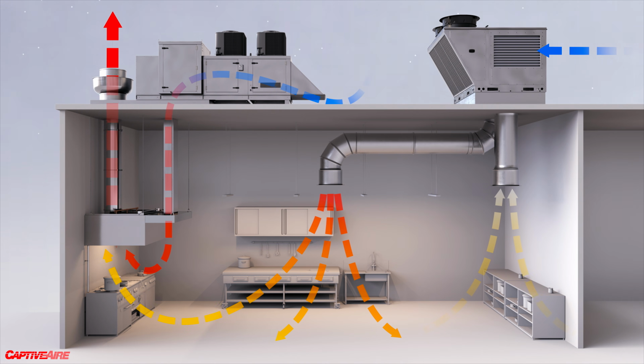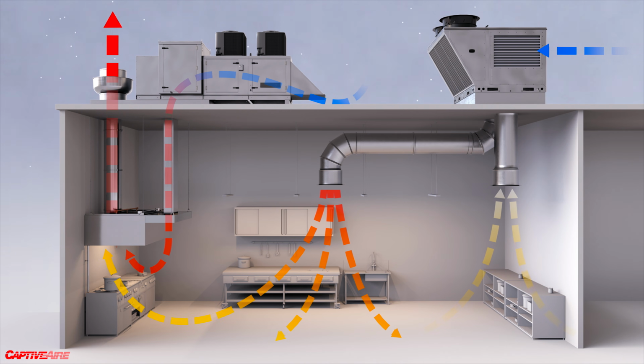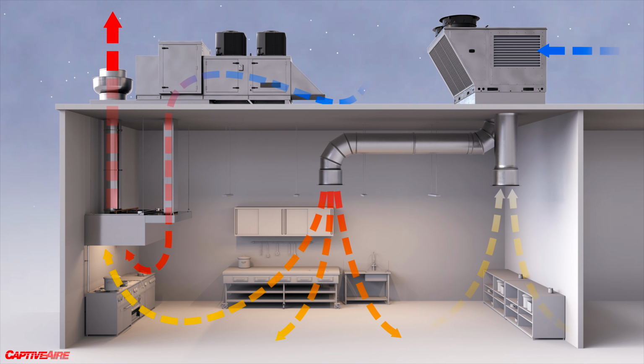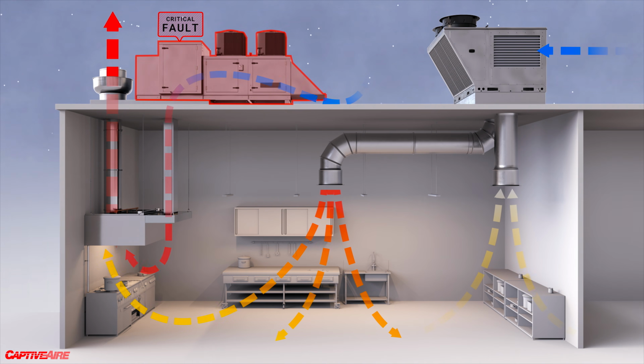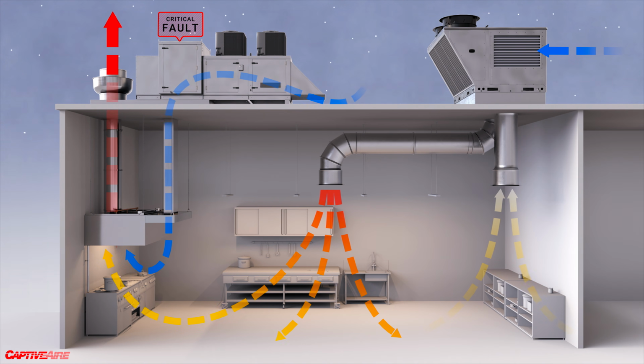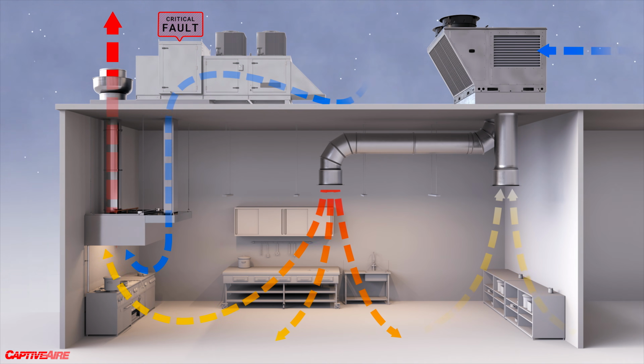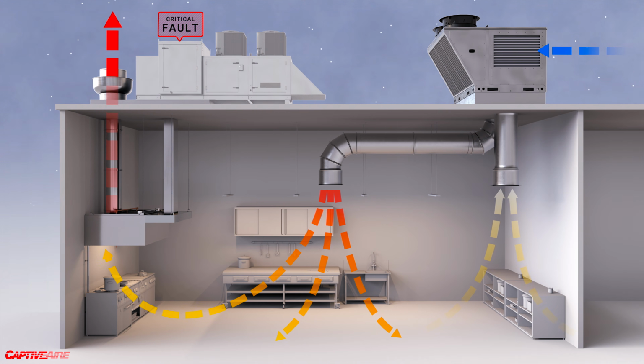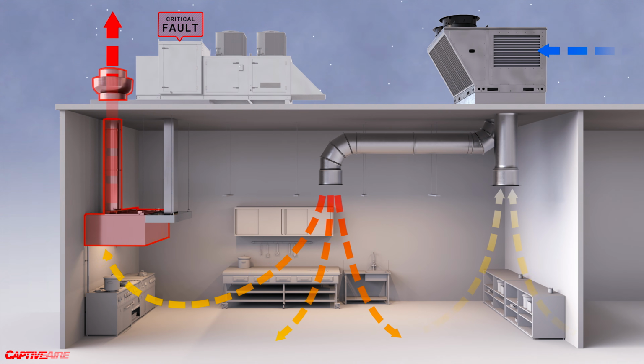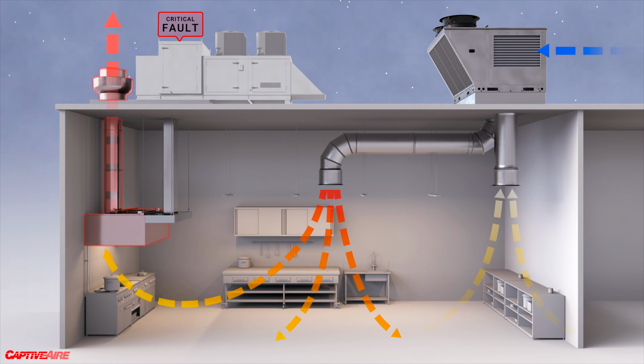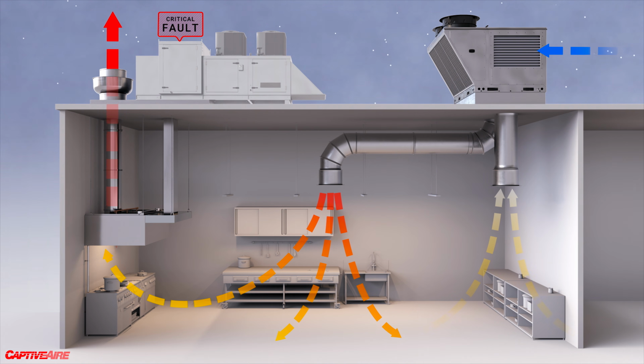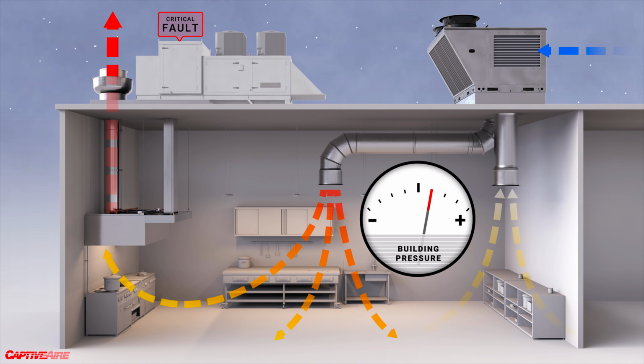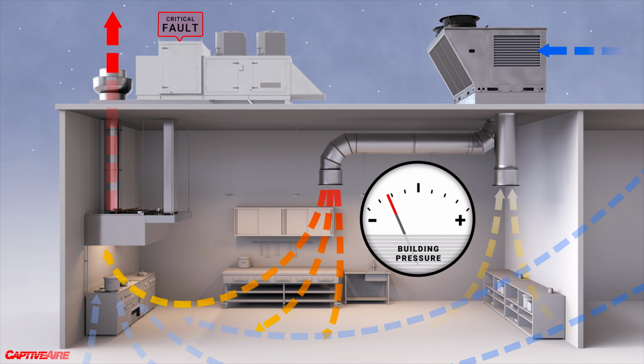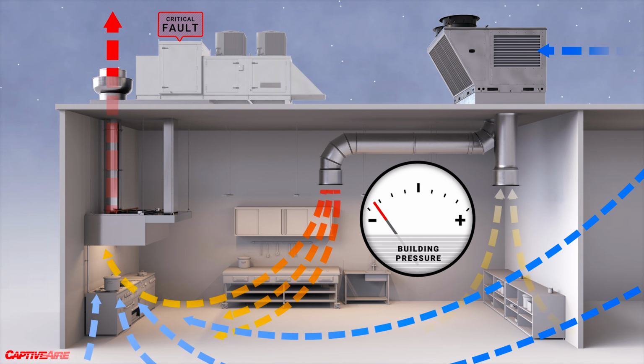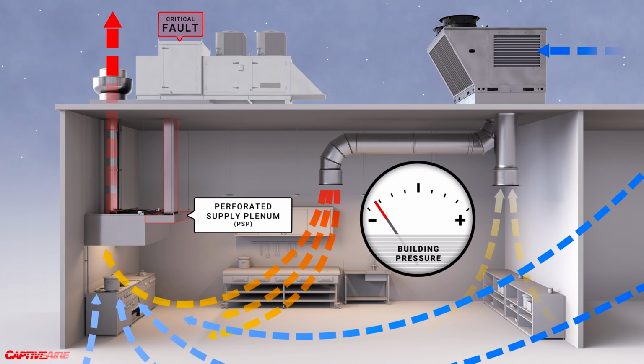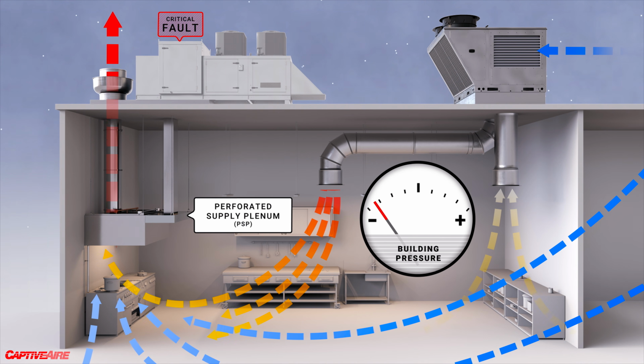What happened is, in the middle of this polar vortex, we had a scenario where the dedicated makeup air unit went into a fault, causing the heat to go out and then the freezestat shutting that makeup air unit off completely. So at that point, we have a hood that's exhausting out all this air and there's nowhere for that air to be made up. We're pulling in air from any place that building can because we're going extremely negative pressure for that building. We had PSPs on the hood that were getting fed from that makeup air unit.